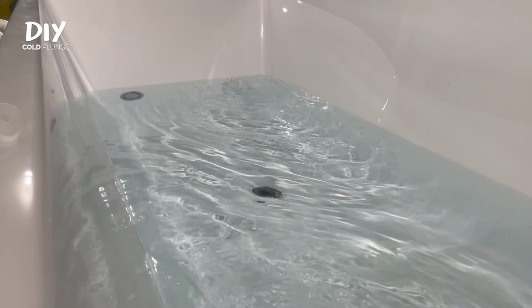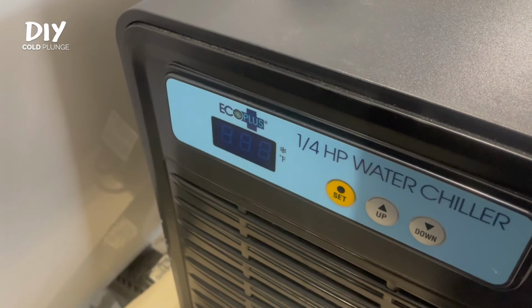I recommend a 24-hour leak test, starting with 12 hours running just your pump. This way you'll be able to check for leaks without battling condensation with the chilled water. Once you've done that and everything's good to go, fire up your chiller and run it for another 12 hours. The reason we want to do both is to, one, clear the hurdle of are there any leaks to begin with, and then two, with that colder water, there's potential for expansion and contraction, and we want to make sure that everything is sealed up enough and stays watertight no matter what temperature it is. And then after that window of time, you know for a fact that your system is either leaking or not.